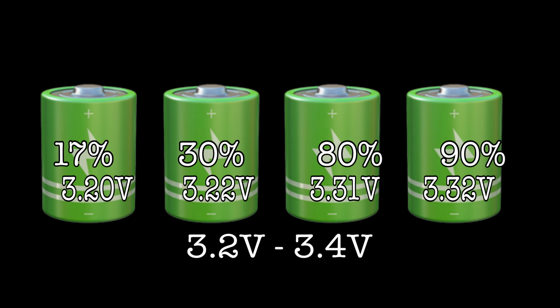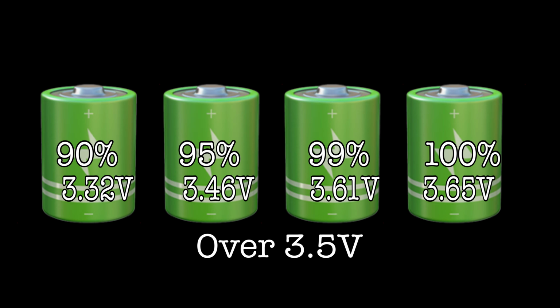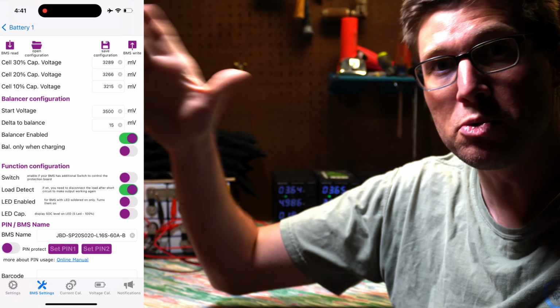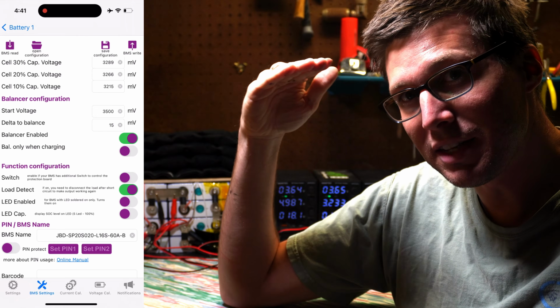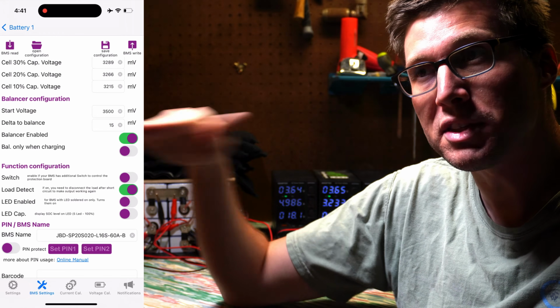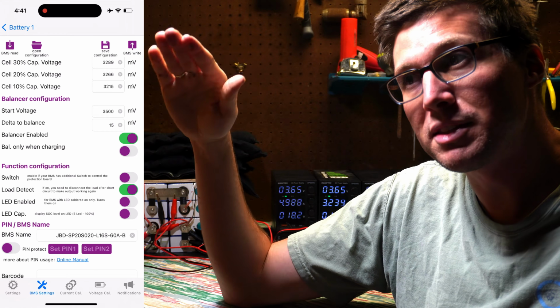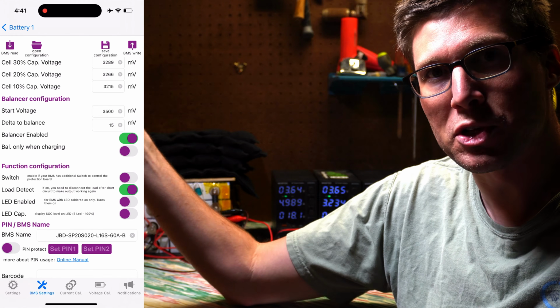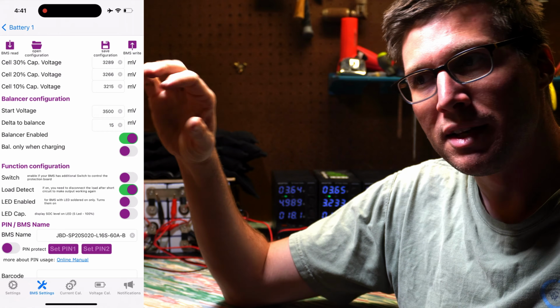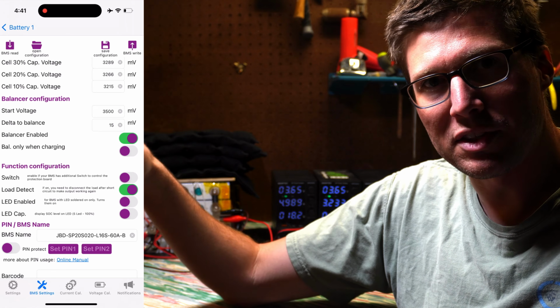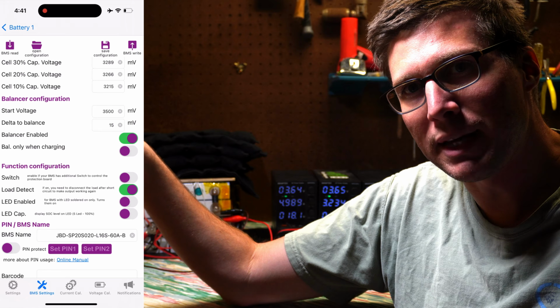Once you exceed 3.5 volts, then any difference in charge is very dramatic — because when one's at, just making up a number here, 98% charge, it'll be at 3.5, and at 99% charge it'll be at 3.62. That's a huge jump. So having it start balancing when all the cells are at 3.5 means it won't start prematurely and won't mess things up, because you want to get them all about the same, but only at the top end.